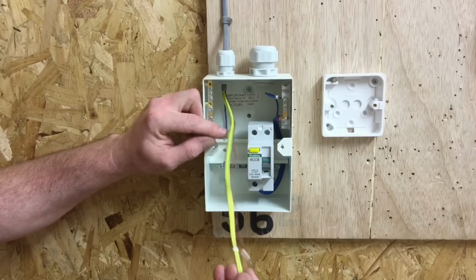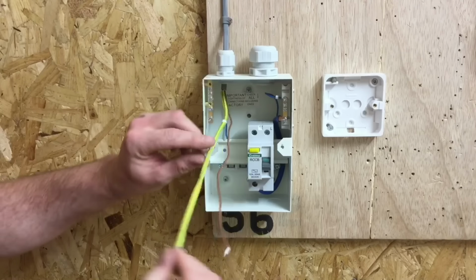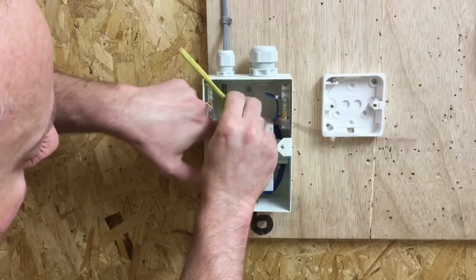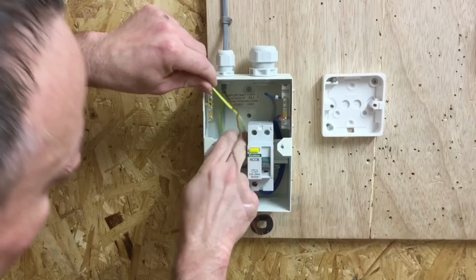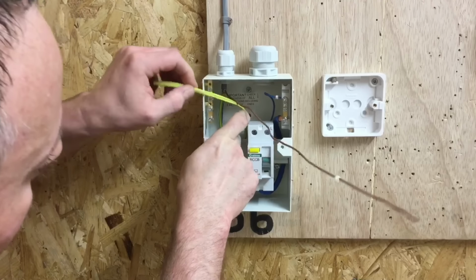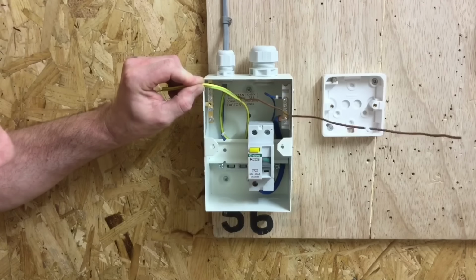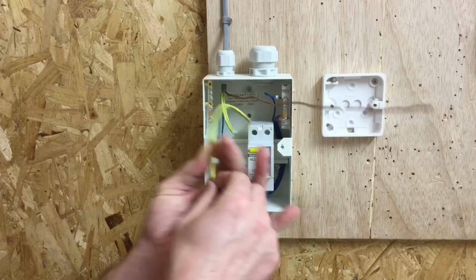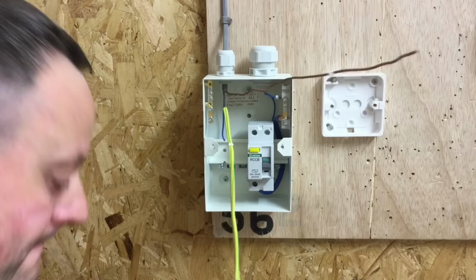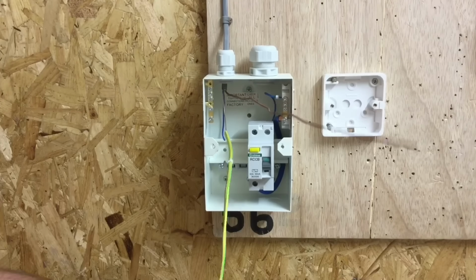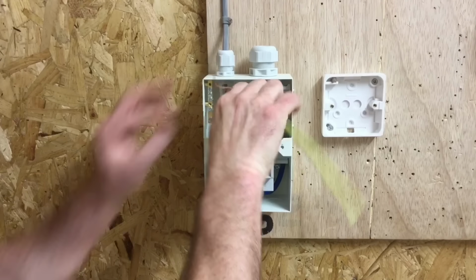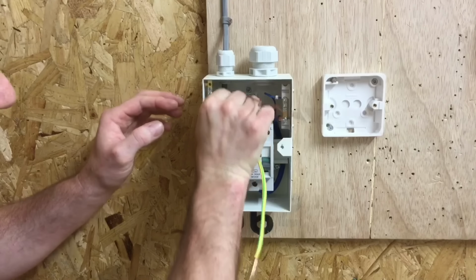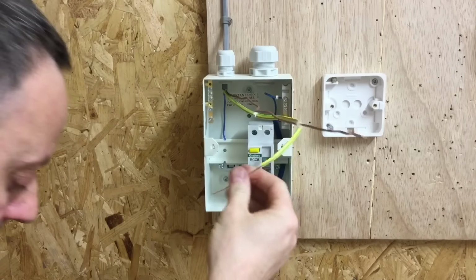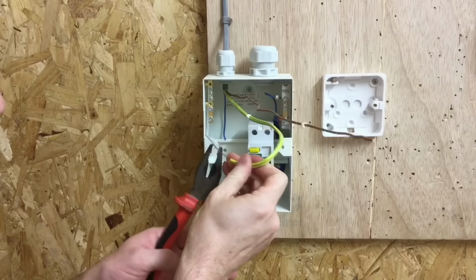So next I'm going to do the CPC. So I've moved my number 1 up out the way. Again, I'm going to come straight down and I'm going to bring it then across and back into the top termination. So it's probably about there that I've got to cut back to. So if I just slide it down and then cut away, hopefully I've got it now a better length for the CPC itself.